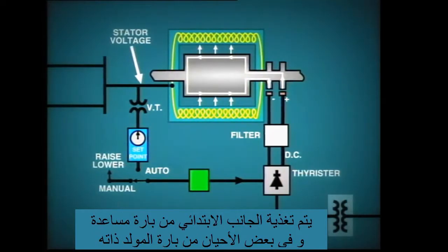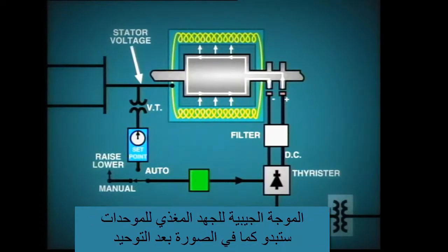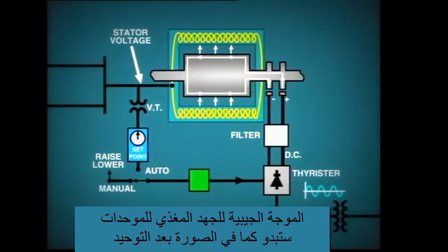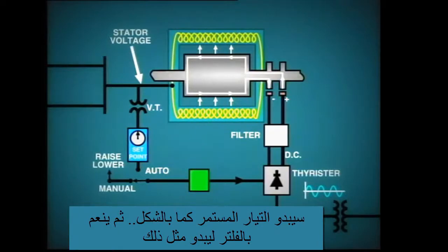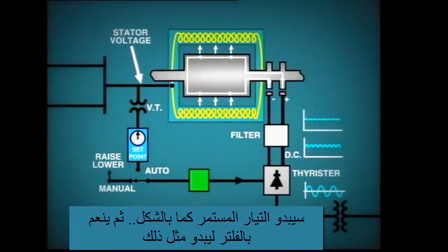The primary side of this transformer is fed from an auxiliary bus, or in some cases the generator bus itself. The sine wave for the incoming three-phase AC voltage, which is applied to the rectifier, will look like this. After rectification, the DC output can be represented by this curve, and this may be further smoothed to look like this.